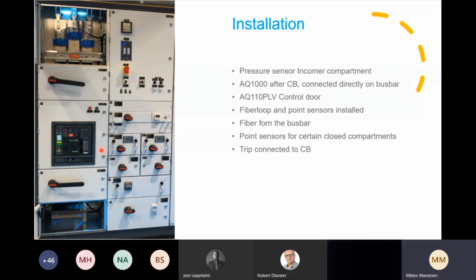And then here's the master relay, and there is a fiber connected to here, and there is another fiber which is connected to the AQ1000 here. So if we have overcurrent here, or an arc flash anywhere in the board, this relay will immediately start opening this breaker. And at the same time, it will make the short circuit to the bus bars with this AQ1000 device.